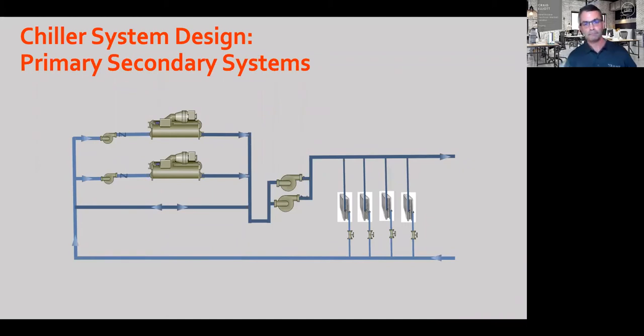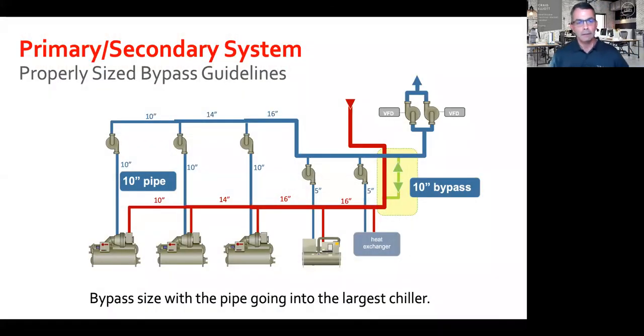Next slide, please. In a primary secondary system, an easy way to determine if the bypass is sized correctly is to compare its size with the pipe going into the largest chiller, as mentioned before. Many chiller plants are tight with minimal space, and usually the hardest task is finding the bypass line, many times due to inadequate room in the chiller plant, tight spaces, which sometimes could be a challenge to find, kind of like where in the chiller plant is Waldo.